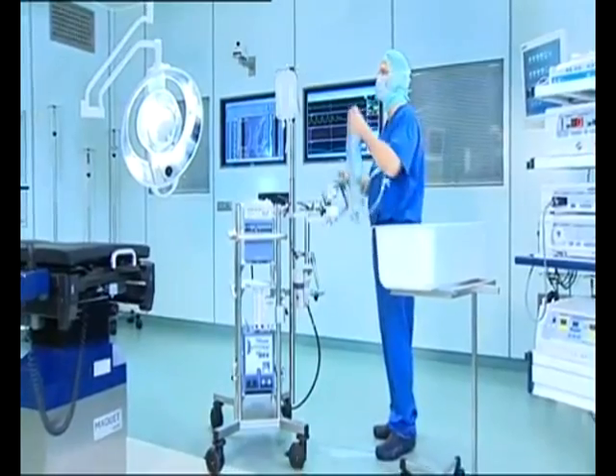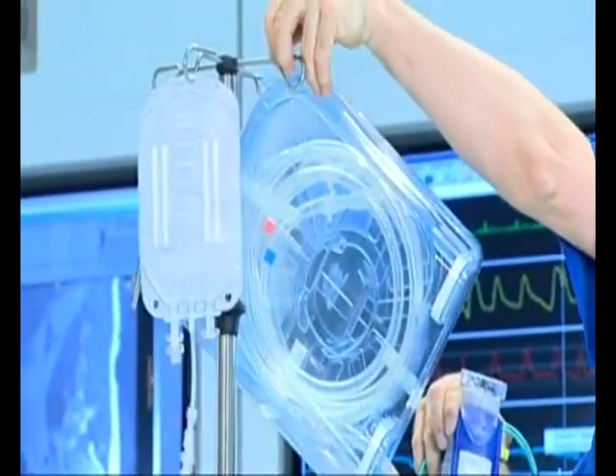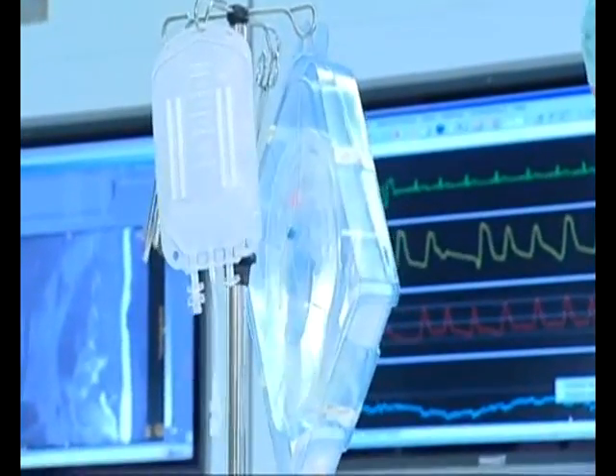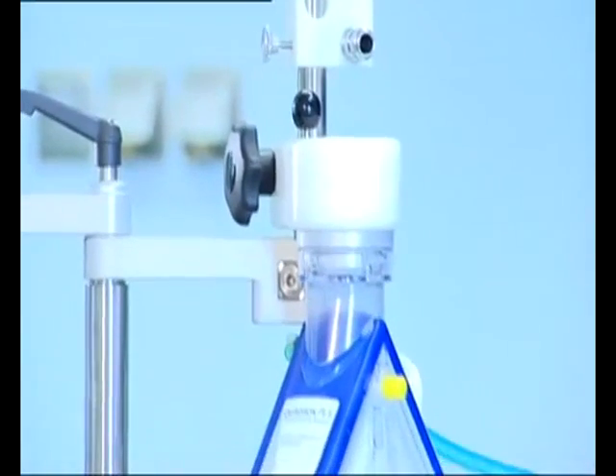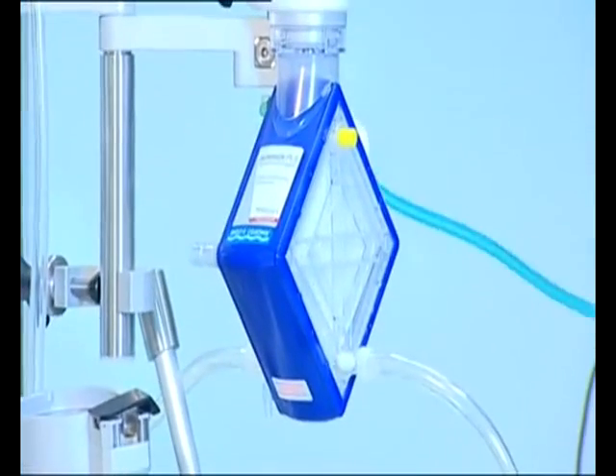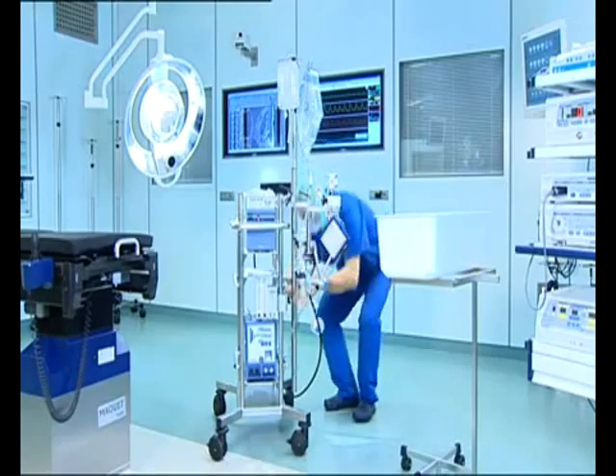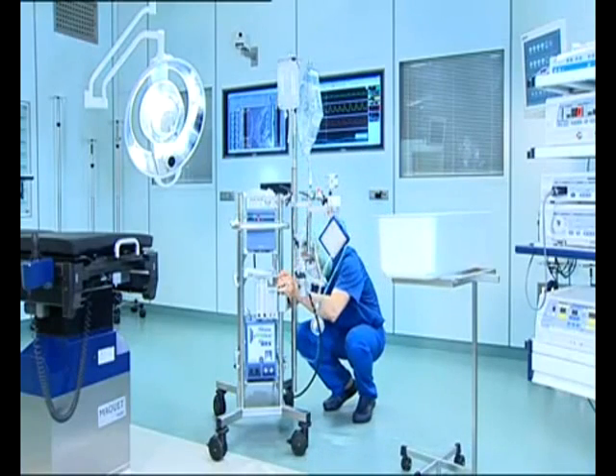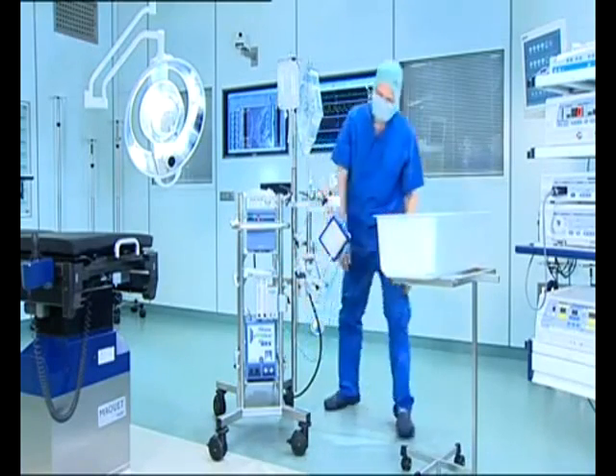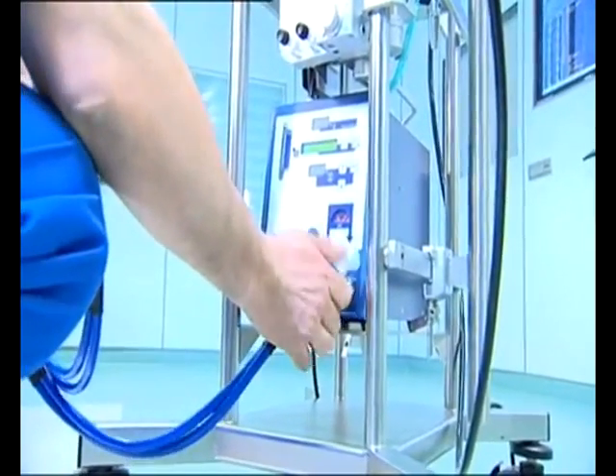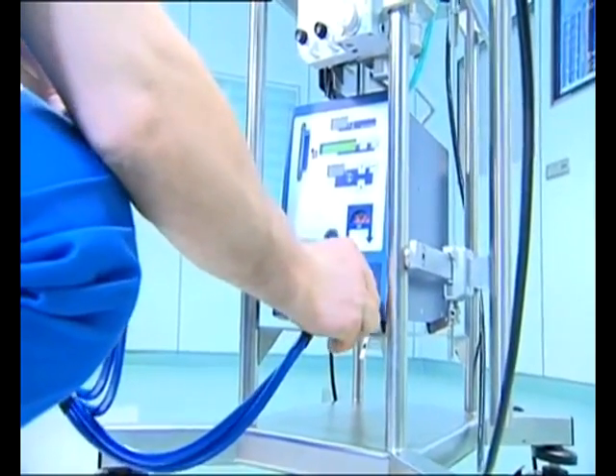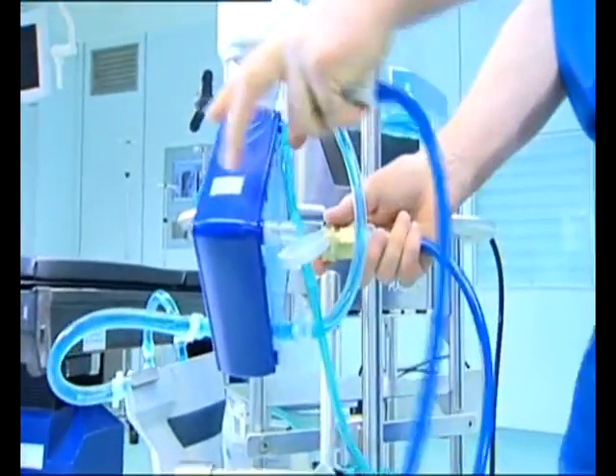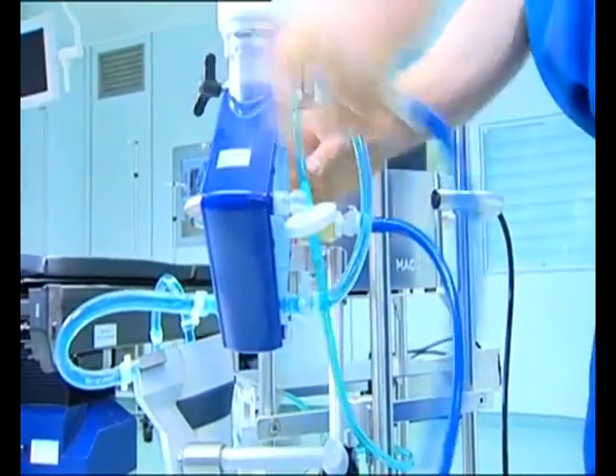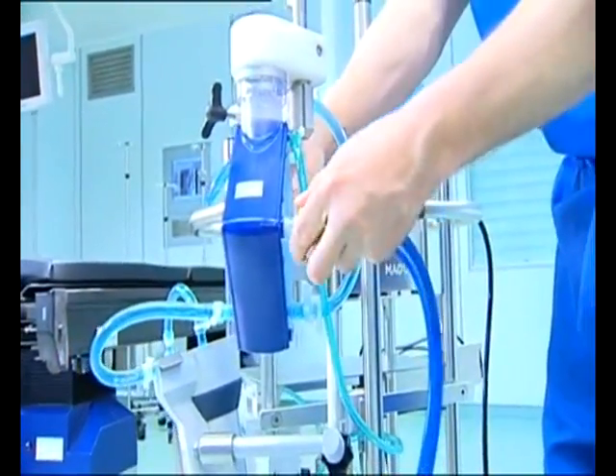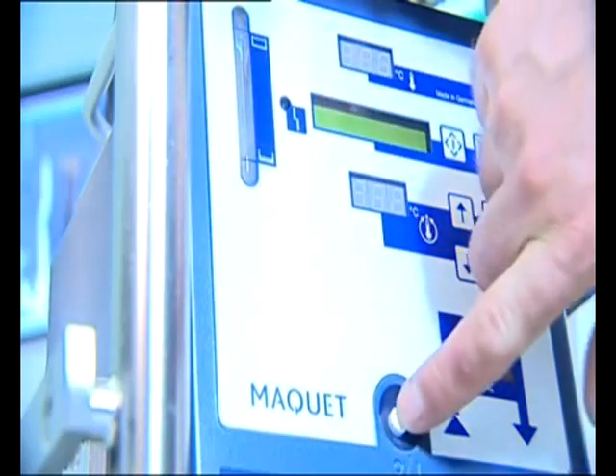While the system is built up and primed, the venous and arterial tubes stay in a sterile and transparent box before use. With a small circular motion, the oxygenator is click-fitted into its holder. Before priming the system, the oxygenator gas and water lines are connected. Now the water flow can be started to confirm heat exchanger integrity.